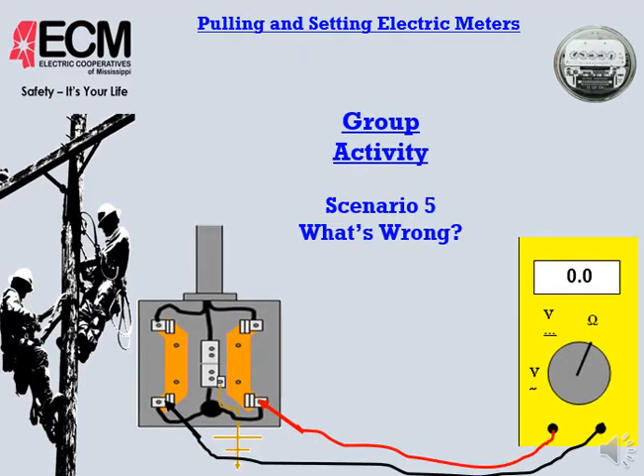And of course we get to this position here, and just real quick, notice that our meter in this position is set in the ohms. We're in the ohm position on our meter, and we're checking phase to phase on our load side. We should get no continuity. It shouldn't be tied together. But in this case, we have it in the ohm position, we're getting zeros, and if we could hear it, you should be getting a tone as well, and that's letting us know that these two bottom conductors are tied together somewhere. If you set a meter in this position with this kind of reading, you're going to get a phase-to-phase fault, and that meter is going to go ballistic.